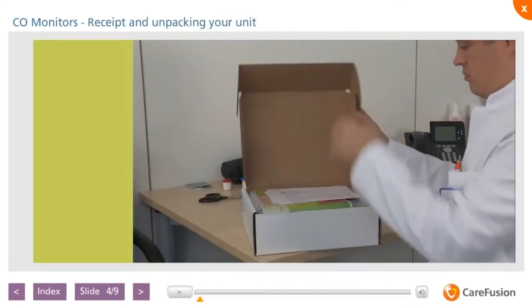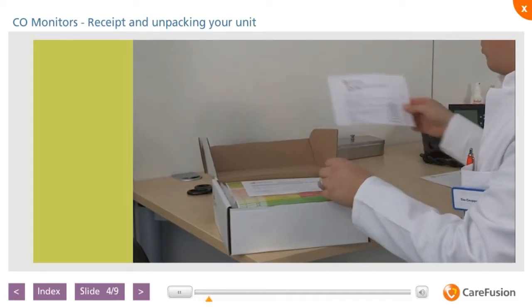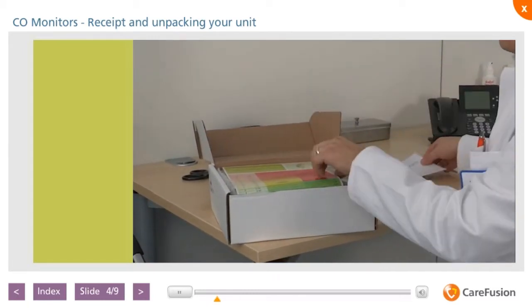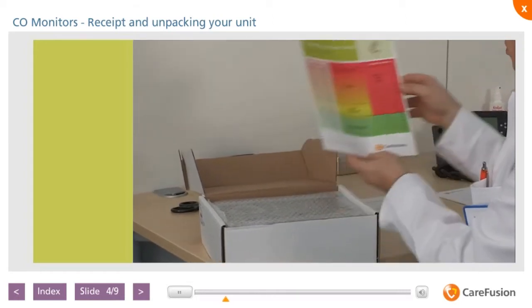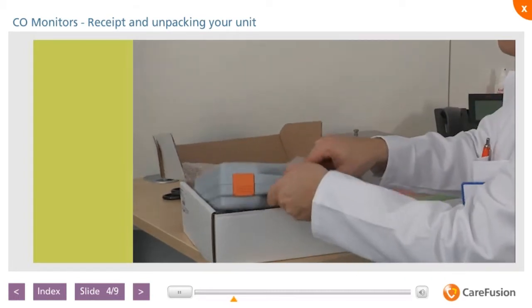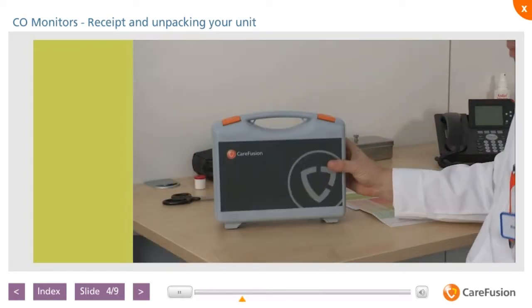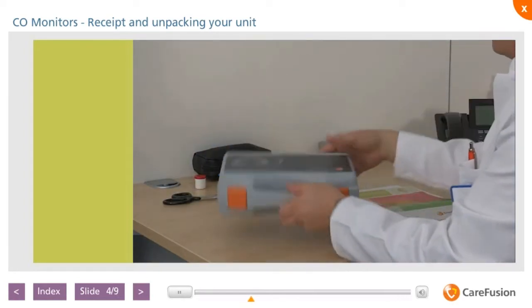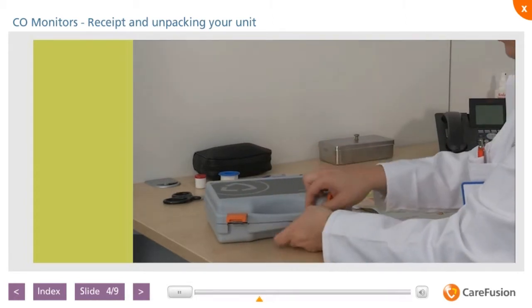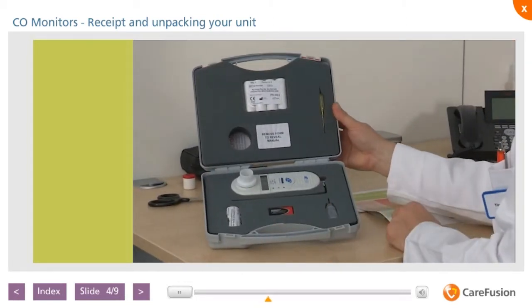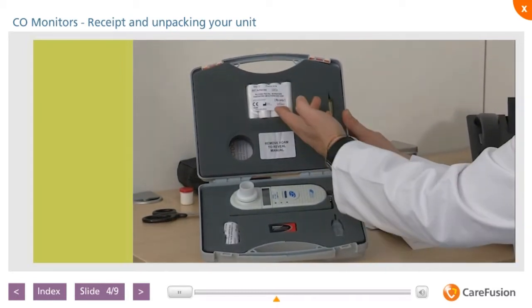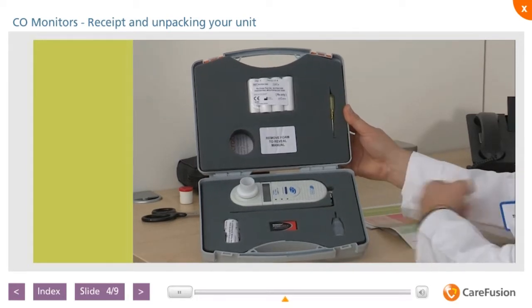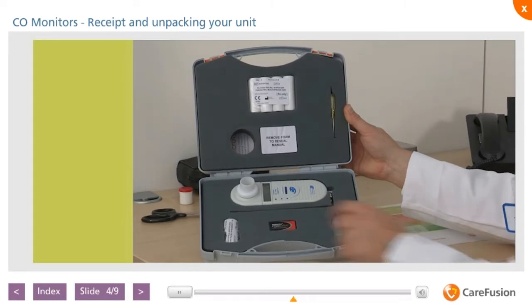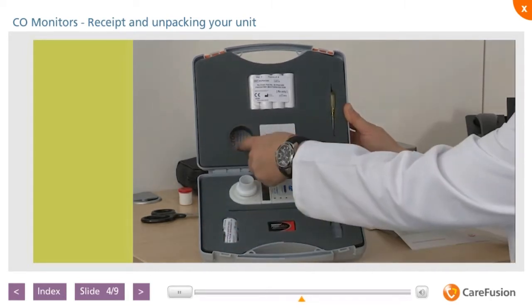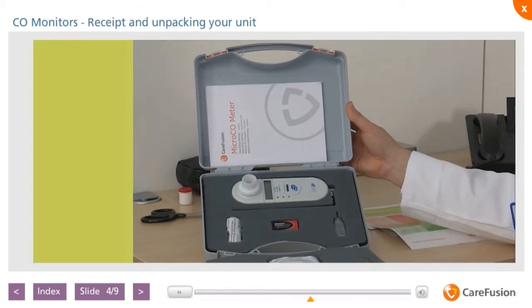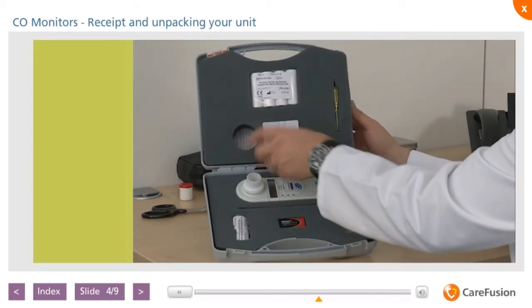The MicroCO is supplied in a white cardboard box. Inside, on the carrying case, you'll find the post-market survey form, the CO measurement table entitled "How High is Your CO?", as well as a content checklist. The unit is supplied in a hard shell carry case as shown. Open the carrying case for access to the unit and all accessories required to perform the initial test. The carrying case contains disposable mouthpieces, a calibration tool, MicroCO monitor, a PP3 9-volt battery, one-way testing mouthpiece, and a calibration adapter. Behind the top foam, you'll find the multi-language module for either the MicroCO, BabyCO or Smoke Check, depending on the model you've chosen.